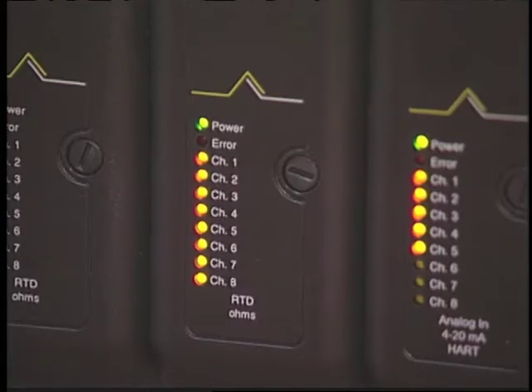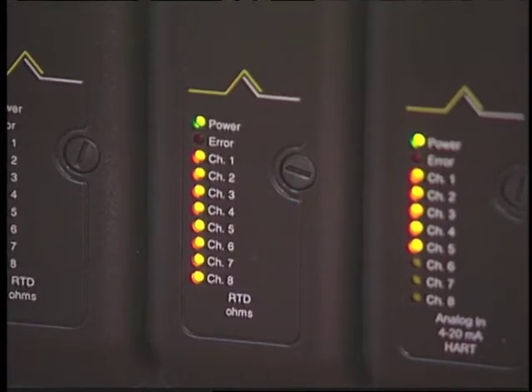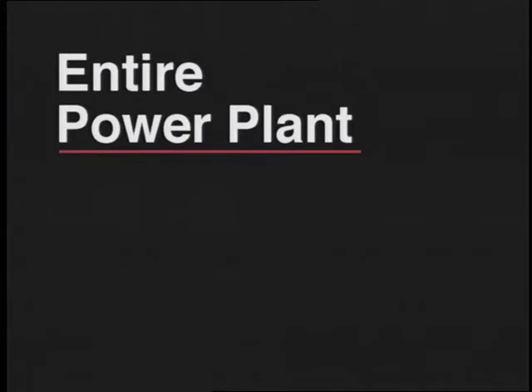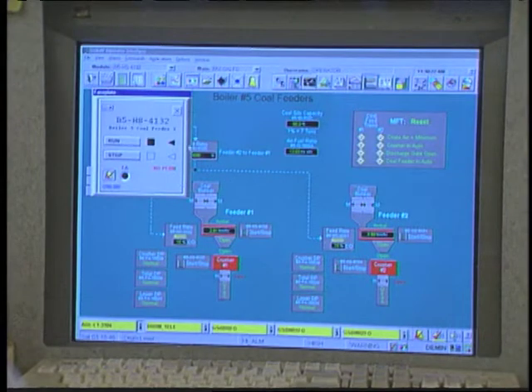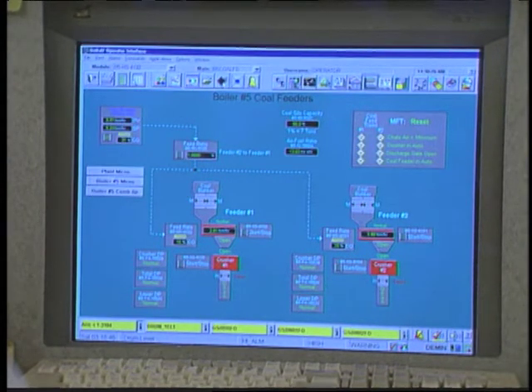With each success, Purdue took advantage of different methods to transition its existing system to DeltaV based on what made the most economic and operational sense to the plant. For example, Boiler 5 right now is still running on the old control system. We changed nothing in the field, didn't have to rewire anything. All we did was add a serial interface that went from the old control system into the DeltaV.